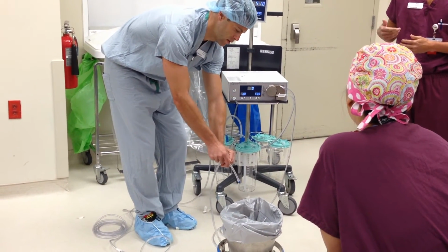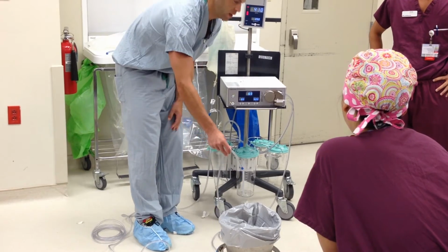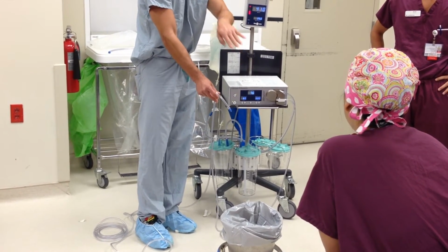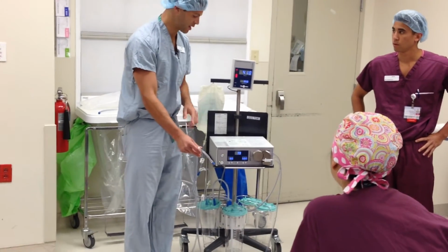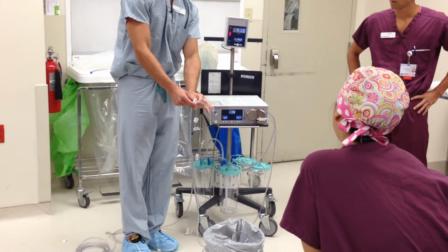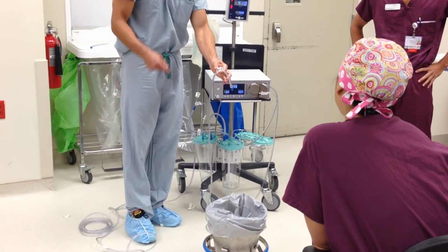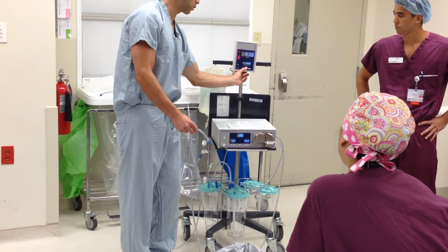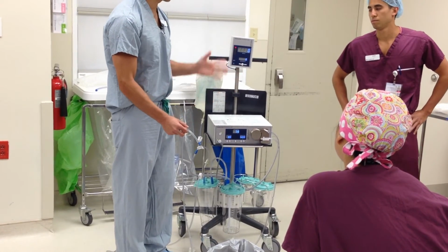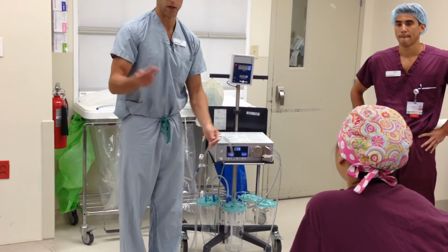During this process, you want to just have the inflow open and the outflow closed. Like this, that's important, or it won't work. Because you want it going through the sheath, coming out the tip. So you heard the second beep. At the second beep, you don't touch this pump again. Just have them clamp it off on the field. And then you can see your deficit showing on 410. So that's when we want to zero this out. So we're at 0. And then you're ready to do the case.